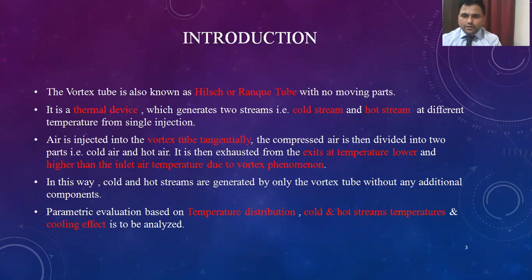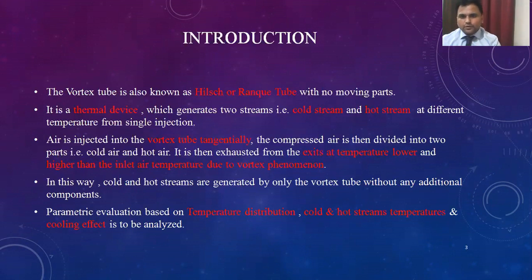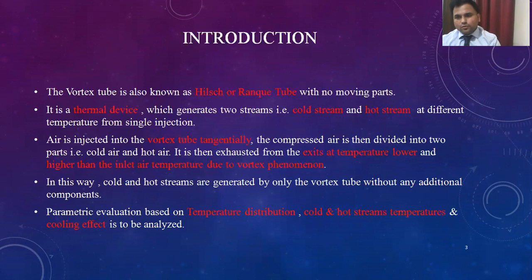Air is injected into the Vortex Tube tangentially, and because of the centrifugal action of the air around the periphery of the Vortex Tube, the air begins to rotate at very high speed. The air enters from the nozzle into the Vortex Tube at very high speed, and the centrifugal action along with the shape of the wall inside causes it to rotate, producing a forced vortex.